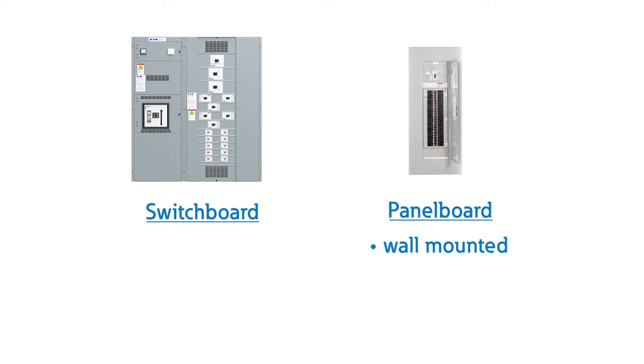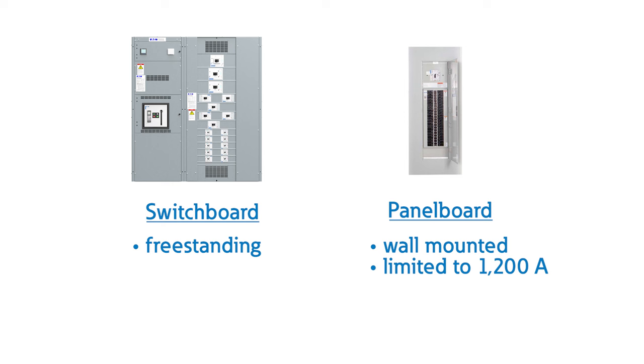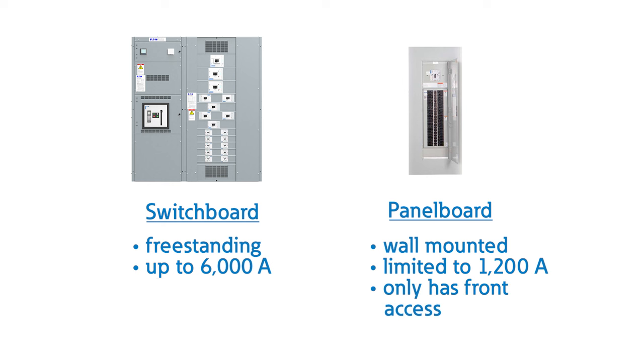What is the difference between switchboards and panel boards? The first thing you would notice is that panel boards mount on the wall, and switchboards are freestanding. Panel boards are designed to UL67 and are typically limited to a maximum of 1200 amps, while switchboards can contain busing and overcurrent devices up to 6000 amps.